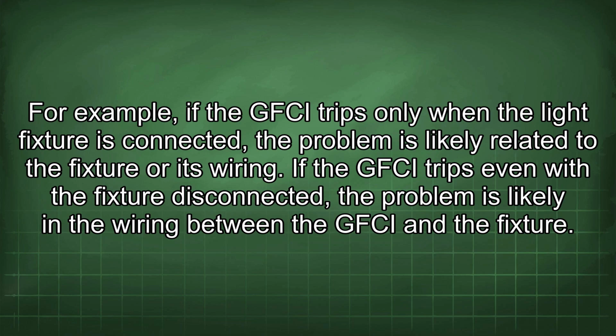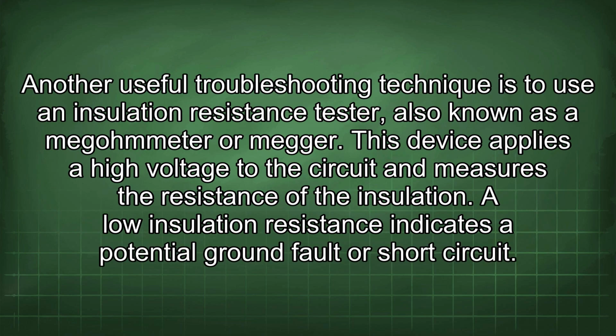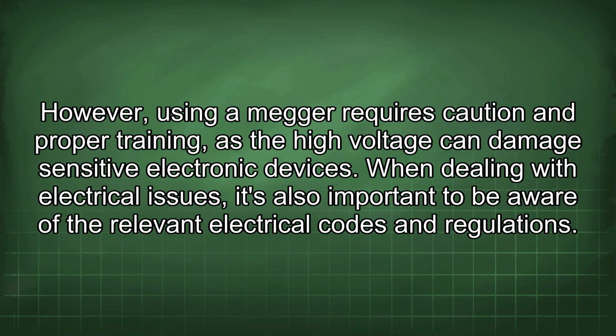Another useful troubleshooting technique is to use an insulation resistance tester, also known as a megohmmeter or megger. This device applies a high voltage to the circuit and measures the resistance of the insulation. A lower insulation resistance indicates a potential ground fault or short circuit. However, using a megger requires caution and proper training, as the high voltage can damage sensitive electronic devices.